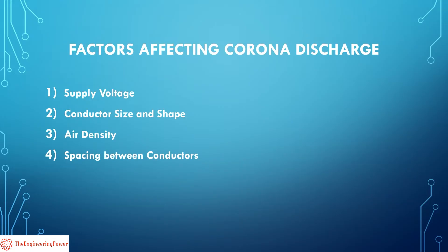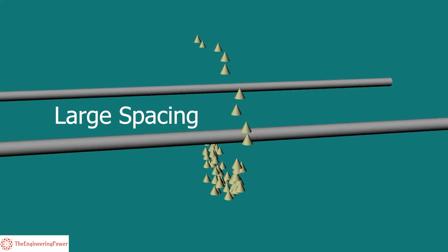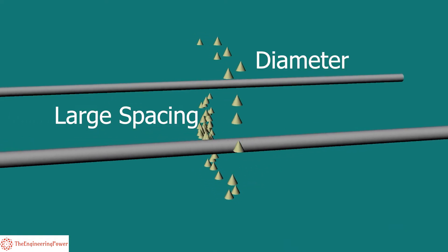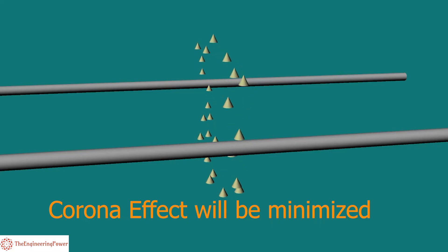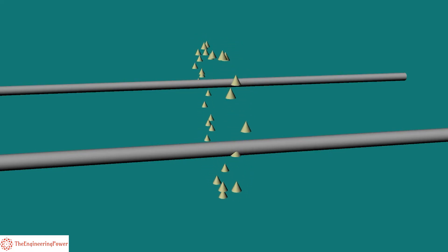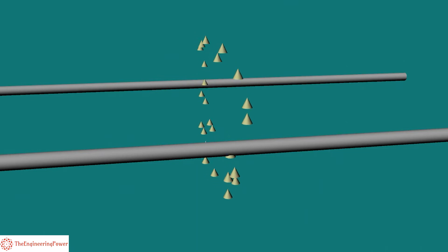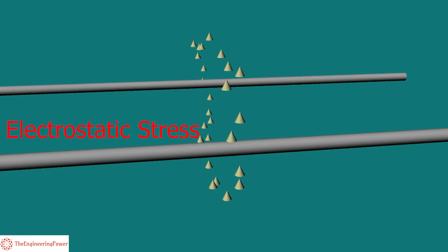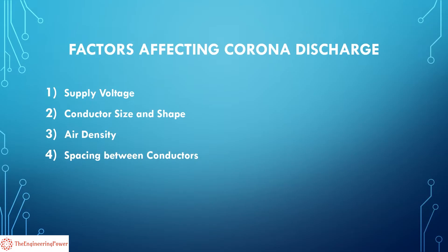Spacing between the conductors also affects the corona discharge. If the spacing between two conductors is very large compared to the diameter of the conductor, the corona effect will be minimized. This happens because by increasing the distance between conductors, the electrostatic stress at the conductor surface is reduced, resulting in very low corona discharge.